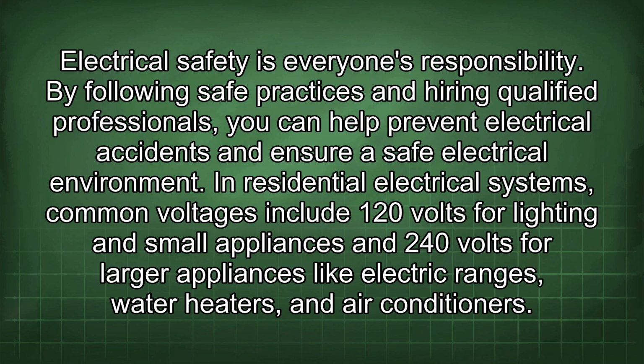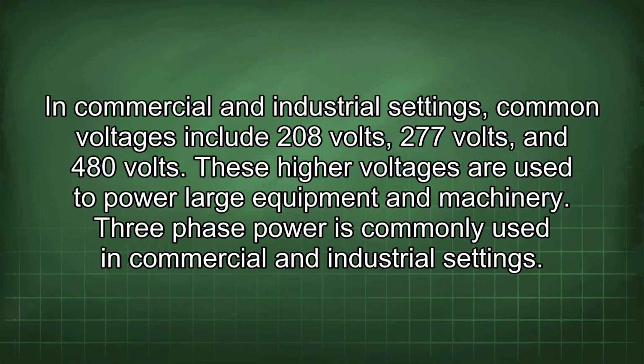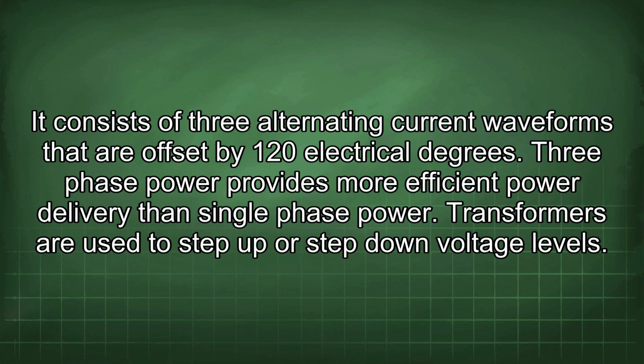In residential electrical systems, common voltages include 120 volts for lighting and small appliances and 240 volts for larger appliances like electric ranges, water heaters, and air conditioners. In commercial and industrial settings, common voltages include 208 volts, 277 volts, and 480 volts. These higher voltages are used to power large equipment and machinery. Three-phase power is commonly used in commercial and industrial settings. It consists of three alternating current waveforms that are offset by 120 electrical degrees. Three-phase power provides more efficient power delivery than single-phase power.